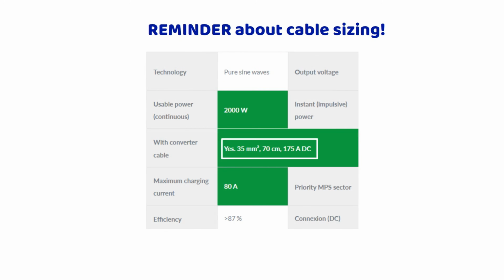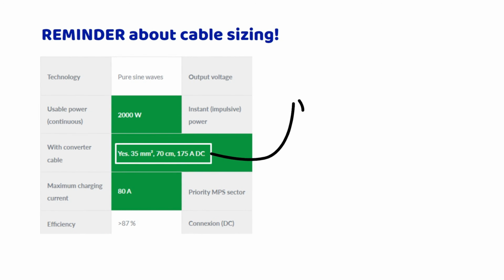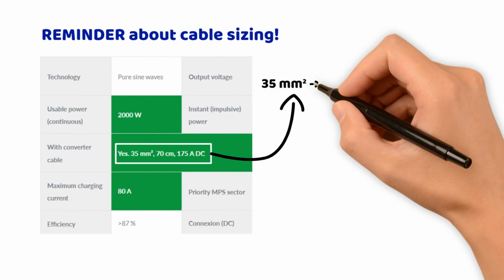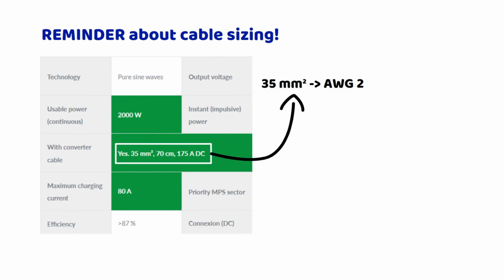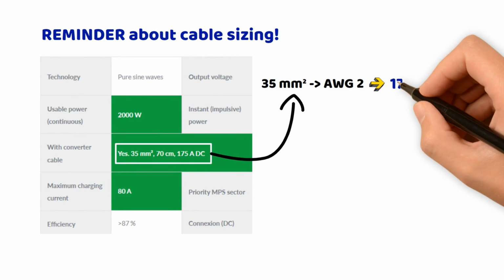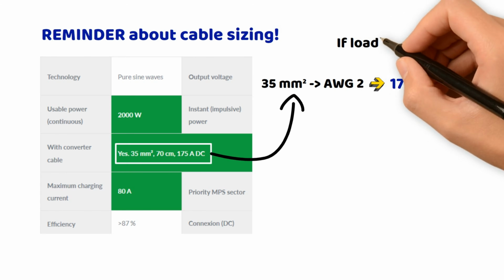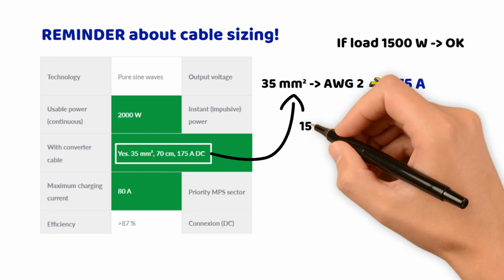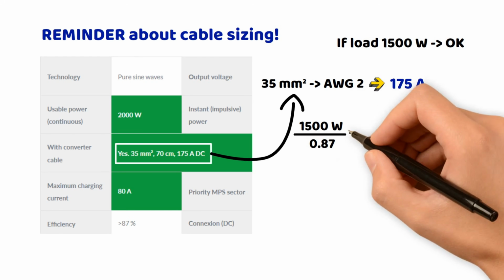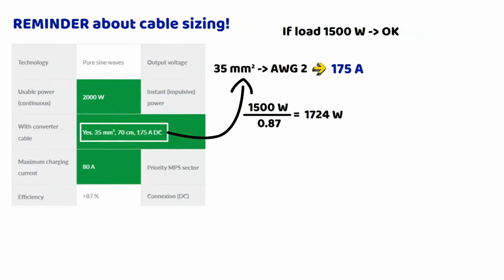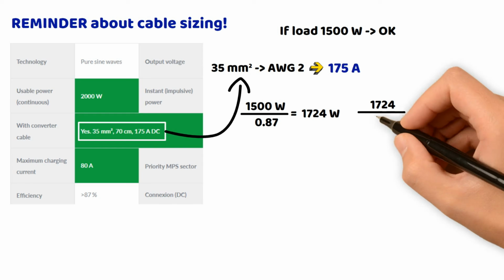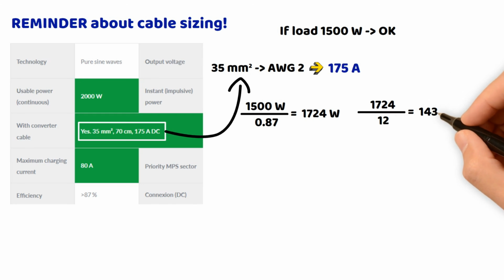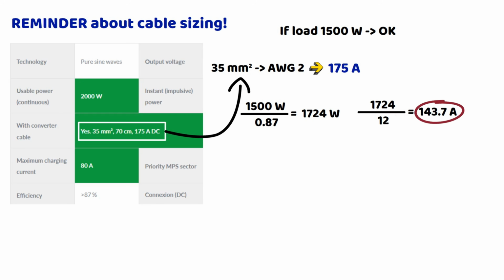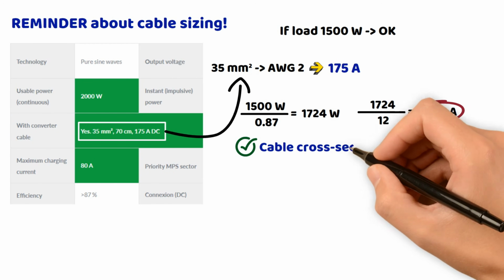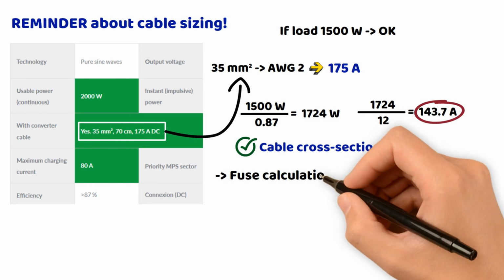In this specific case, the converter comes with 35 square millimeter cables, or AWG2, but it is stated that they are limited to a current of 175 amperes. This is specified in practice. If you use a 2000 watt converter to connect a 1500 watt device, there's no problem. 1500 divided by 0.87 equals 1724 watts. 1724 divided by 12 equals 143.7 amperes. With 143.7 amperes, you are below the cable limit. In this specific setup, for a 1500 watt device, you do not need to change your cables.